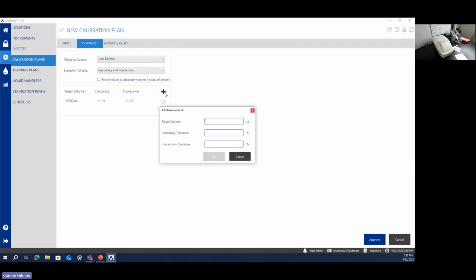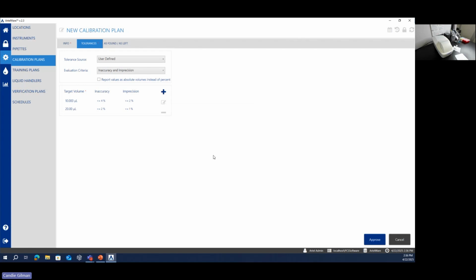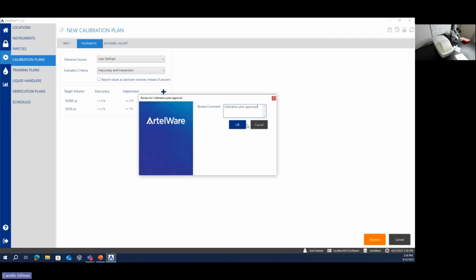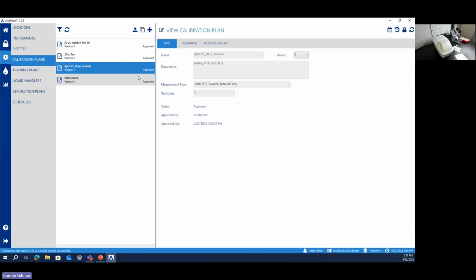And then I'm also going to test this pipette at 20 microliters. And yet again, I've got some user-defined tolerances that I'm going to add. And then I'm just taking a look back through. I'm going to test this pipette today for you at 10 microliters and at 20 microliters. So I'll go ahead and select approve. And now that calibration plan is in my list. So I'm going to go ahead and head back to the home screen.